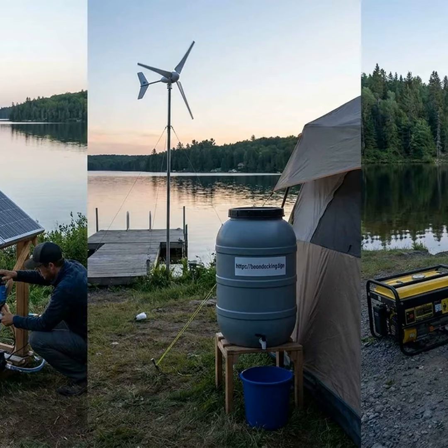Battery bank: to ride out sandstorms or a dust-covered week, we install a 48-volt, 800 amp-hour bank, about 38 kilowatt-hours, of LiFePO4. This covers 3 days of consumption. LiFePO4 is chosen for safety and thermal stability. However, high daily charge-discharge cycles and heat will age them faster.